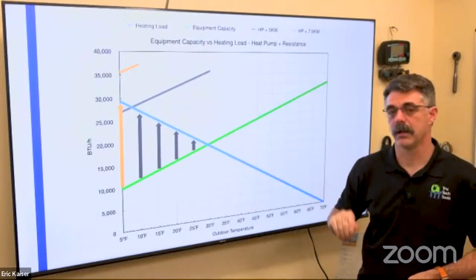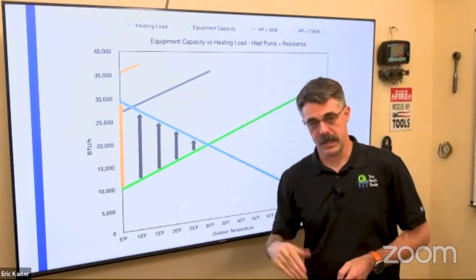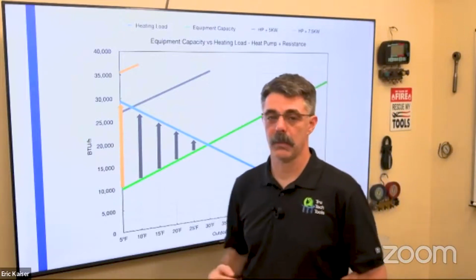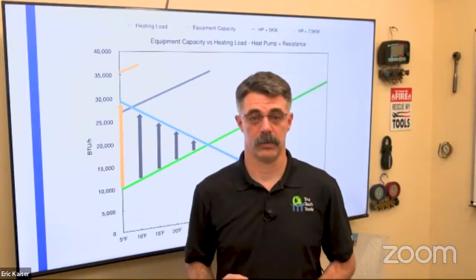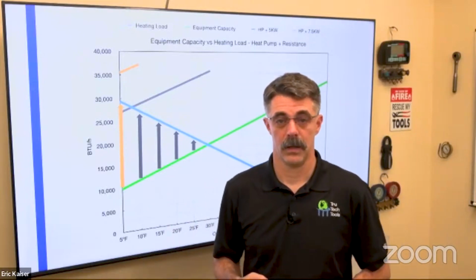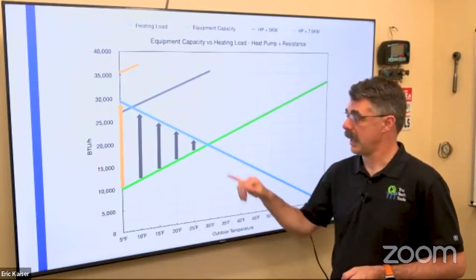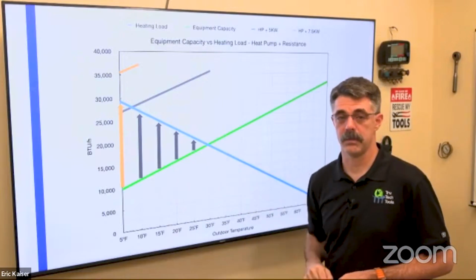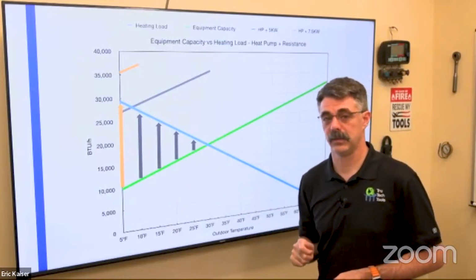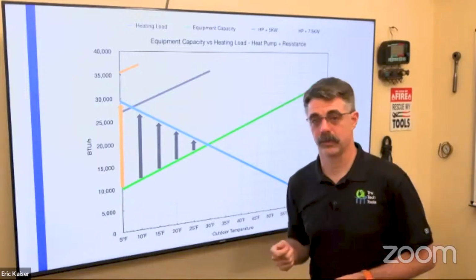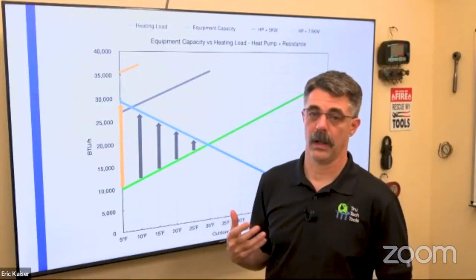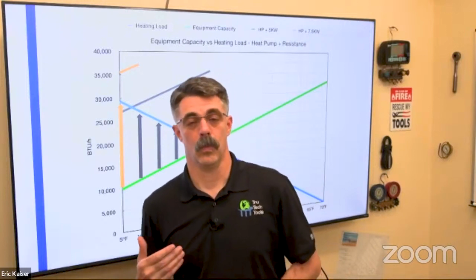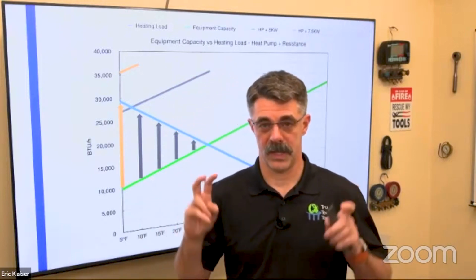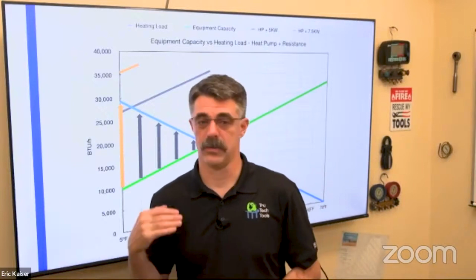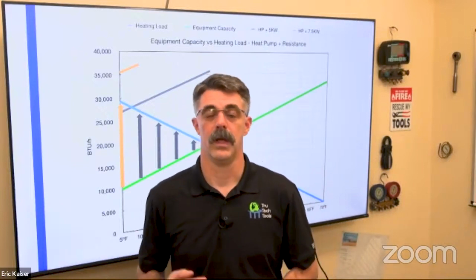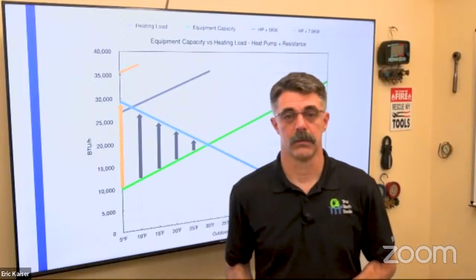But roughly around here at 29 degrees, the heat pump in heating mode will no longer be able to keep up with the demands of the house. Okay. Now, if you remember that COP chart, it's still cheaper to run the heat pump down here than it is to run straight electric heat. Now, a lot of people will say, once your heat pump stops heating or loses performance or can't keep up with the house, you should just turn it off and run electric heat. And I can say from experience that's incorrect.